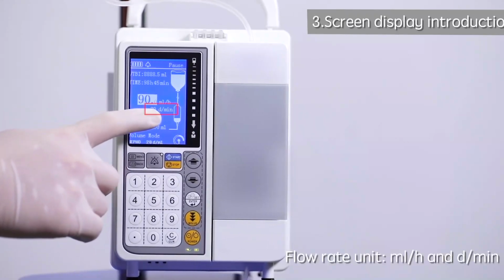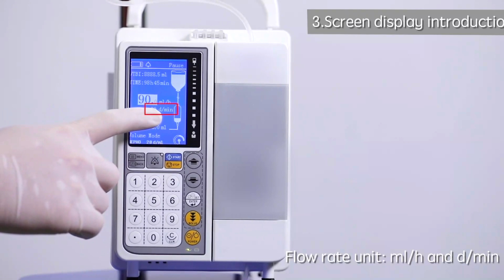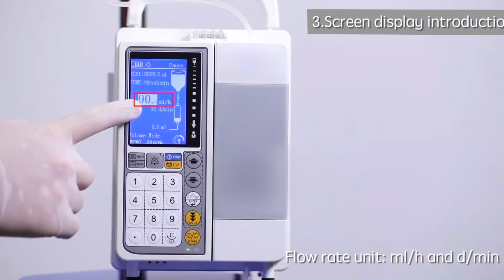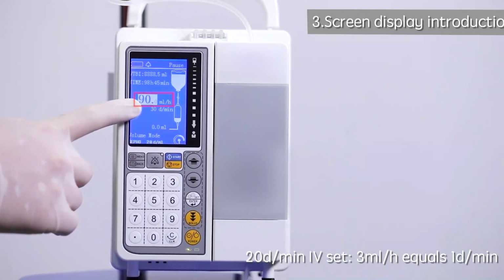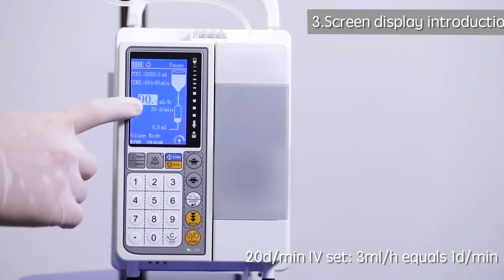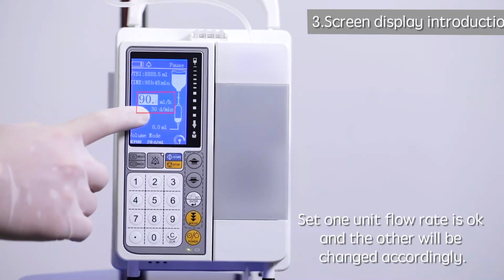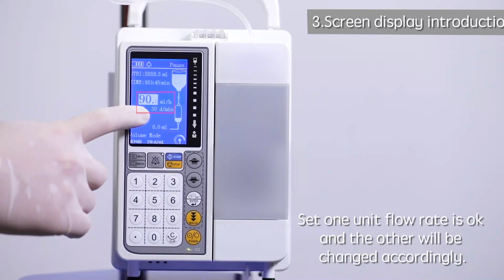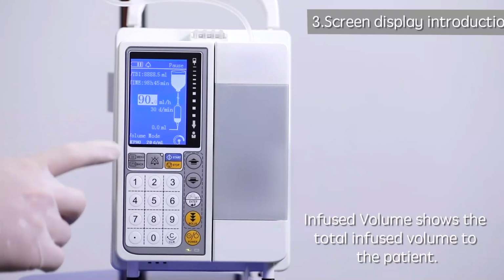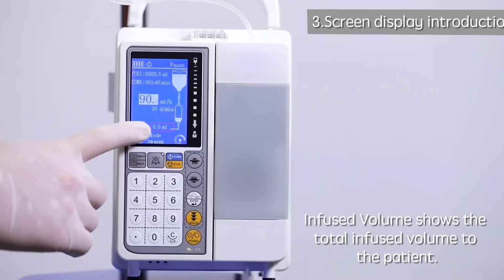Flow rate unit: milliliters per hour and drops per minute. For a 20 drops per minute IV set, 3 milliliters per hour equals 1 drop per minute. Set one unit of flow rate, and the other will be changed accordingly. Infused volume shows the total infused volume to the patient.